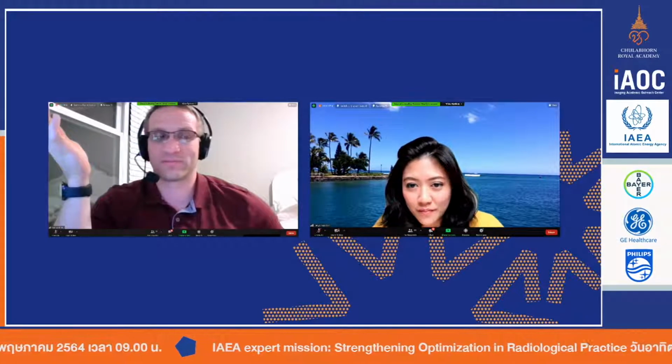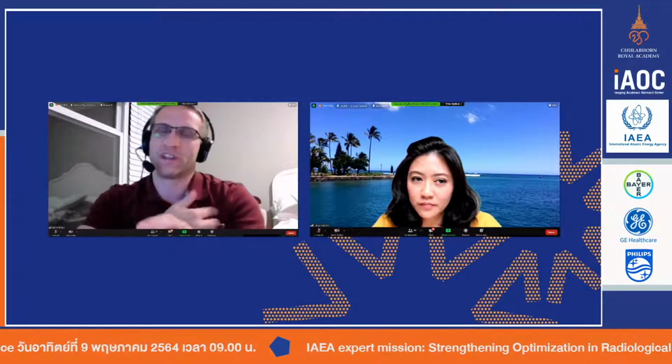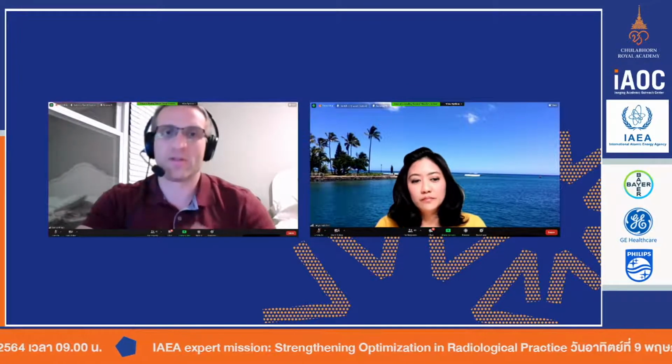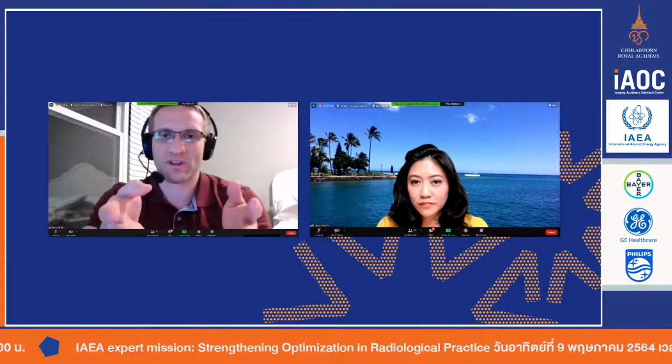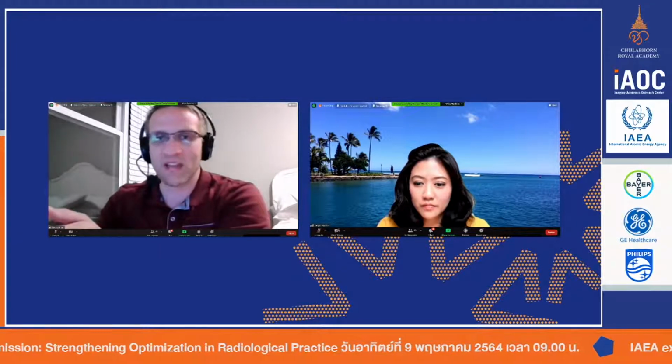If your target values are not appropriate, I mean, what does DI mean? A DI is just the ratio of the value for the protocol for the patient in that moment to the target. So if your target of the chest, now I showed you my value, it was about 420. And if you, for whatever reason, actually set it at 200, well, that means the vast majority of your images are going to have a really high DI number. They're all going to be 7, 8, 9.